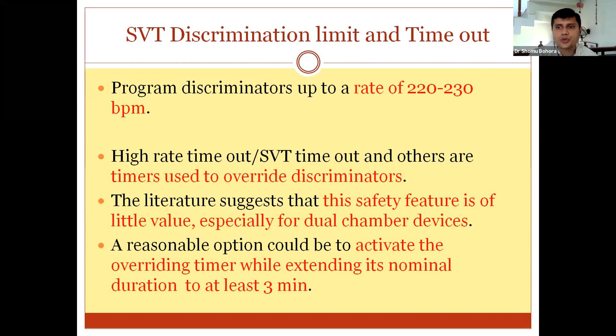So if it is for primary prevention, there is no VT, you are thinking it's only going to be VF, the programmed ventricular detection can be set at a higher ventricular rate for avoiding shocks. Morphology criteria should always be on. Stability criteria should be on for atrial fibrillation, while onset criteria for sinus tachycardia. Timeout and onset do not help, but an SVT limit should be considered if you have a documented atrial arrhythmia which goes beyond a 200 rate limit.